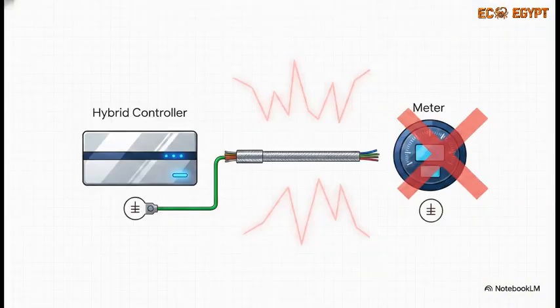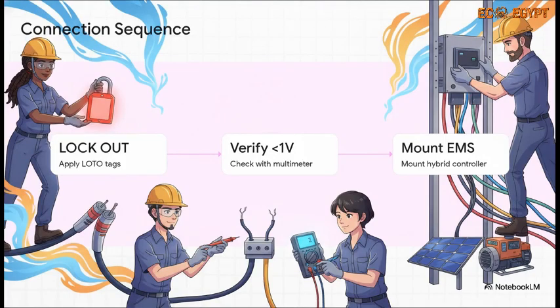Now listen up, because this is a massive warning for the step-by-step wiring connection. The RS-485 cable has a metal shield. You must ground that shield at the controller end only. If you ground it at both ends, you create a massive ground loop. It will completely scramble the Modbus signals. And if your controller can't talk to the inverters, your entire energy island collapses. And speaking of physical wiring, the absolute first step is high-stakes safety. You have to lock out all grid, generator, and DC sources before a single wire is energized. Remember, power here flows from multiple directions: the solar plant, the BESS units, and auto-starting DG. Because of that, verifying zero energy with a multimeter is a life-saving, non-negotiable step.